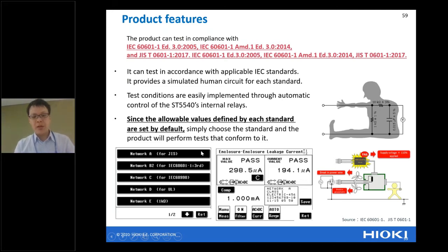Okay, so if you turn on the ST5540, you can find this kind of display. You can see all of the standard numbers. If you want to do IEC 60601-1, in that case, please push the network B2 like this. In addition, Hioki already checked the standard, so that's why Hioki already set the default setting for the threshold of the leakage current comparator. So you can just open the network and test. It's very easy.